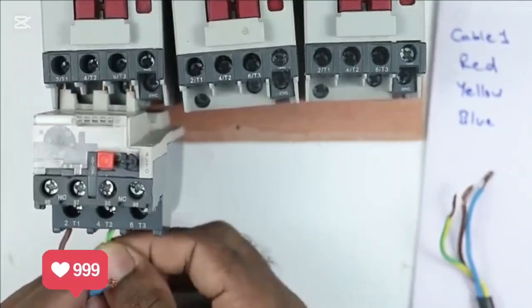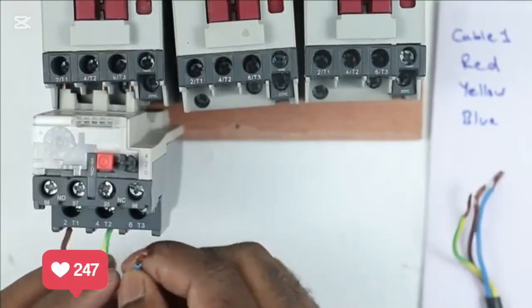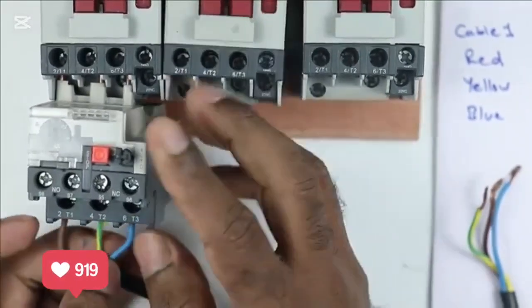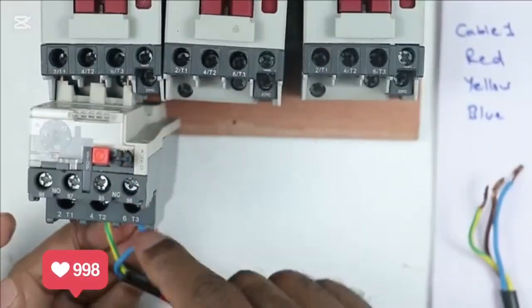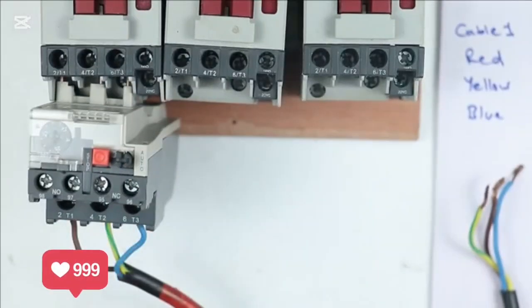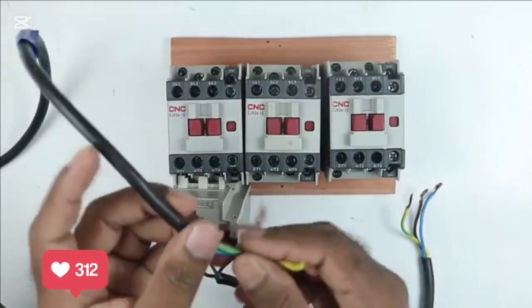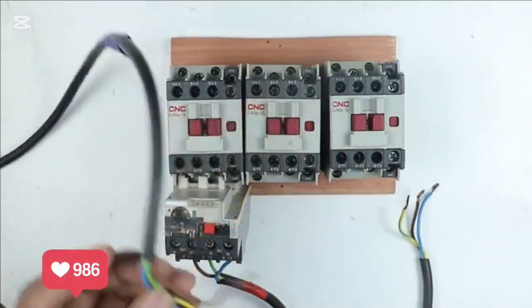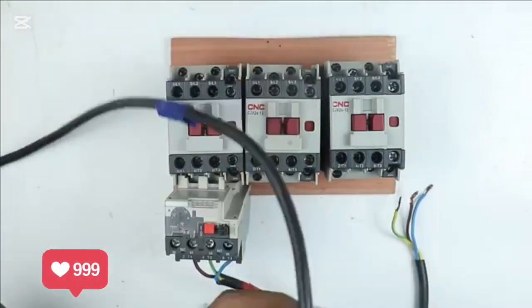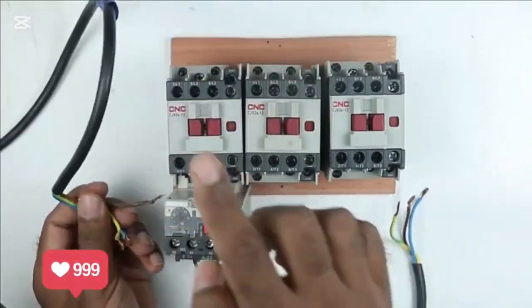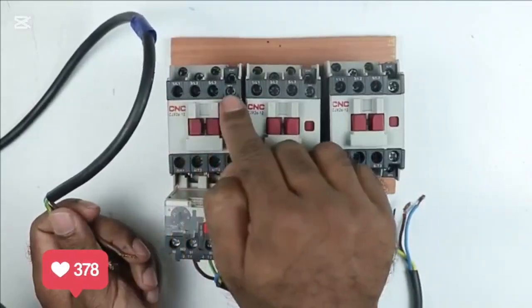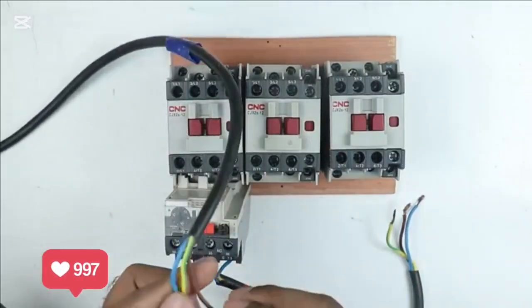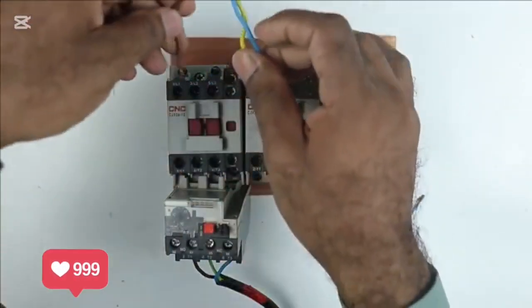At T2, you have to connect Y phase power supply, and at T3 terminal, you have to connect B phase power supply. So R, Y, B in this sequence, you have to connect the wires. After this, the main incoming power supply you have, I mean the 3-phase power supply coming from MCB, take this power supply and connect it to this main contactor at these upper terminals. So I will connect the wires according to phase sequence only.